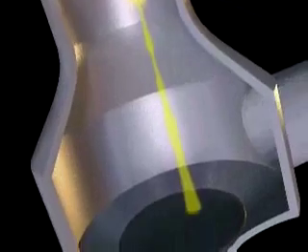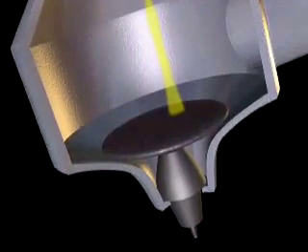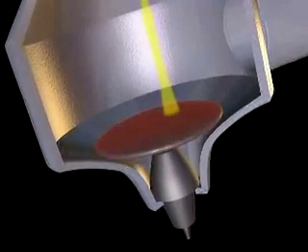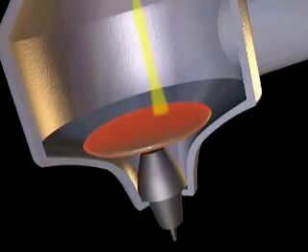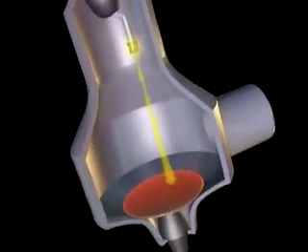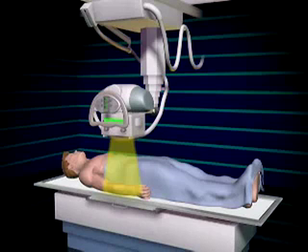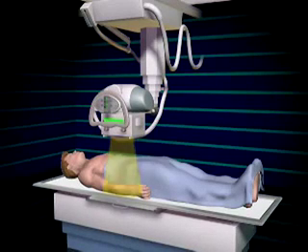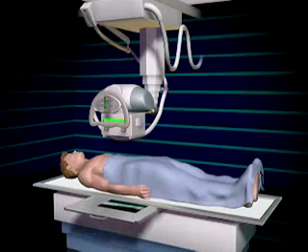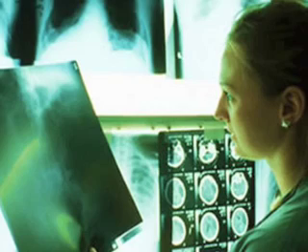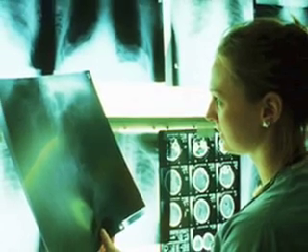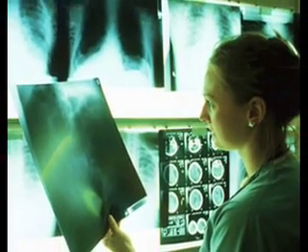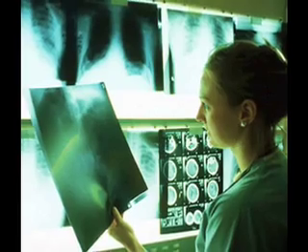X-rays are generated by an X-ray tube, a vacuum tube that uses a high voltage to accelerate the electrons released by a hot cathode to a high velocity. The high velocity electrons collide with the metal target, the anode, creating the X-rays. In medical X-ray tubes, the target is usually tungsten or a more crack-resistant alloy of rhenium, 5%, and tungsten, 95%, but sometimes molybdenum for more specialized applications, such as when soft X-rays are needed as in mammography.